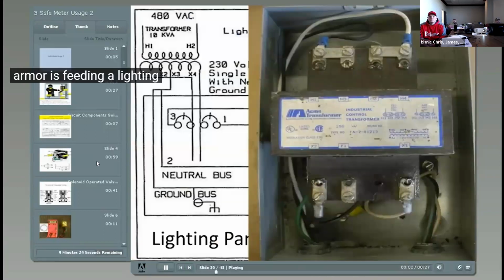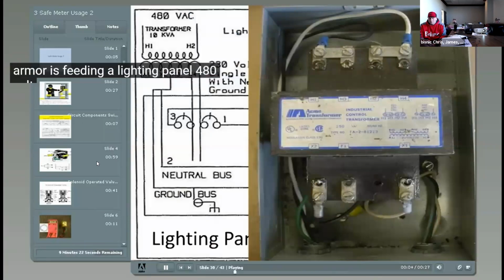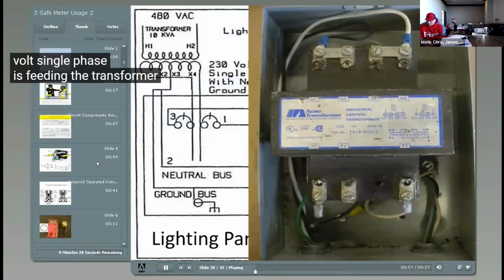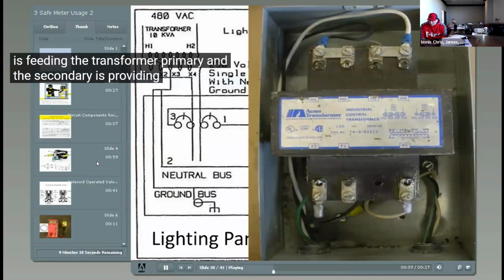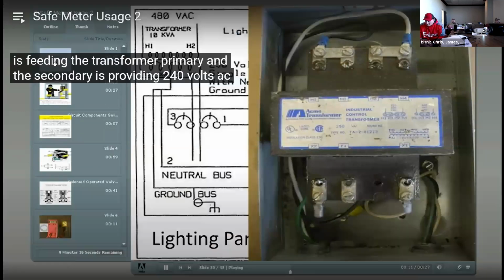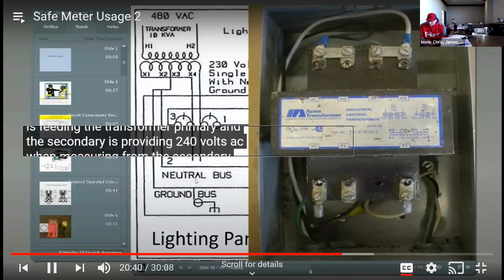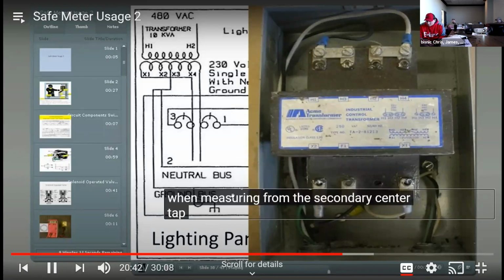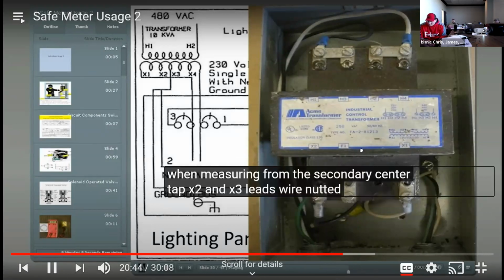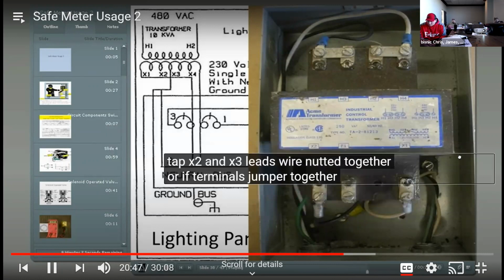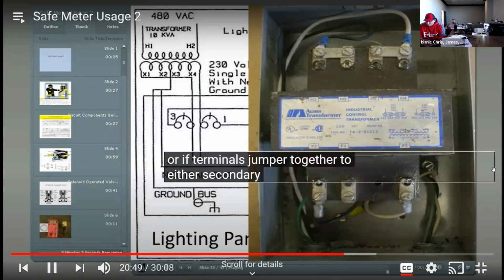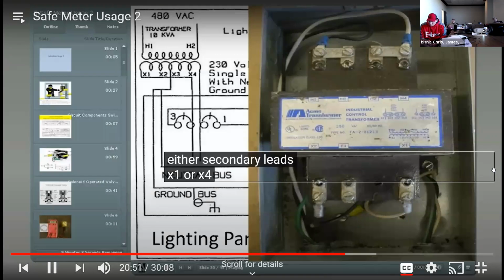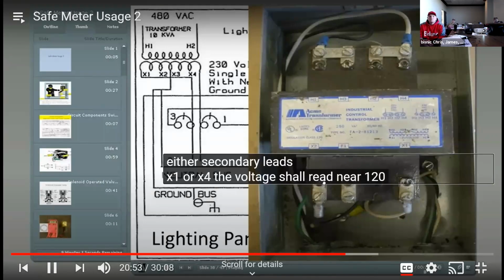The transformer is feeding a lighting panel. 480 volt single phase is feeding the transformer primary, and the secondary is providing 240 volts AC. When measuring from the secondary center tap, X2 and X3 leads wire nutted together, or if terminals jumper together, to either secondary leads, X1 or X4, the voltage shall read near 120 volts AC.